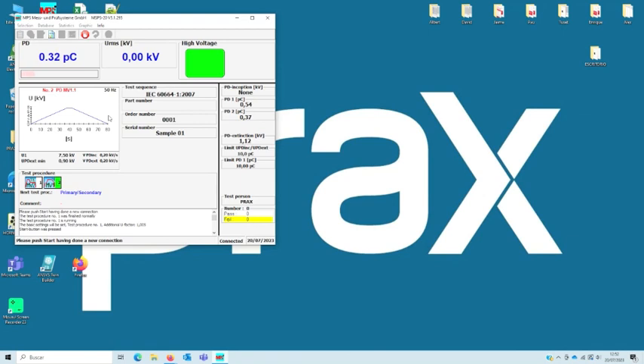Now the second test would be the extinction voltage. Here basically we would like to see what the real extinction voltage is, in order to see how far we are from the working voltage. For this test, we increase the voltage until we have partial discharge. Once we have partial discharge, we wait some seconds, and then we decrease the voltage until we have partial discharge below 10 picocoulombs. This voltage is considered the extinction voltage and would be the maximum allowed voltage to work between primary and secondary side. So now we will perform the test.